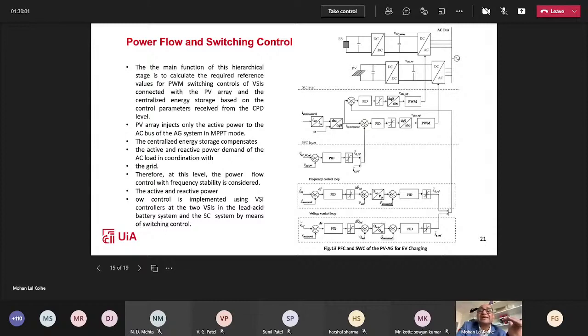And here we have this control unit. In the control unit, the PV array is going to inject only the active power to the AC bus, operating at unity power factor. But the centralized energy storage is going to compensate the intermittency of the photovoltaic with grid constraints. You have to keep in mind the grid constraints.